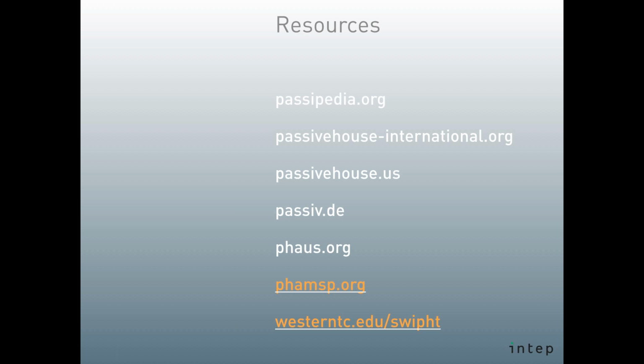Interestingly, the passive house is actually a model where a forced air system works much better—we sort of have it backwards. In conventional construction, with large heat loads and low surrounding temperatures, a radiant heat system makes you much more comfortable. But in this well-insulated model, all you're really conditioning is the air inside, and that's where forced air shines, because it does that very quickly and efficiently. So the traditional way of building is sort of exactly backwards, and we find these systems here very cost effective.